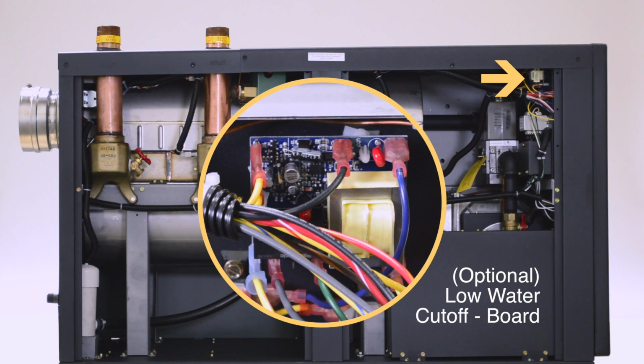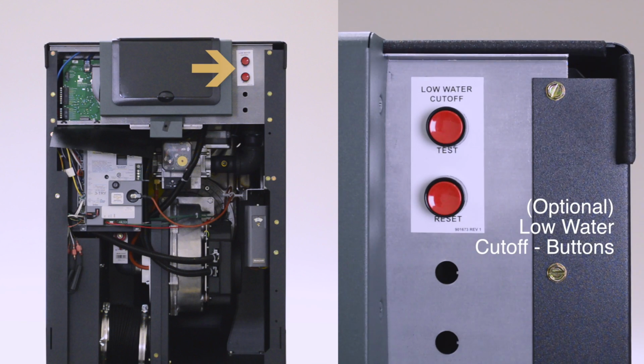The low water cutoff board has a red LED light. If the unit is running properly and there is no air in the water lines, the red light will remain lit. There is a test button and reset button on the front of the unit. The test button confirms that the low water cutoff is working. The reset button reestablishes the low water cutoff after air has been purged from the water lines.